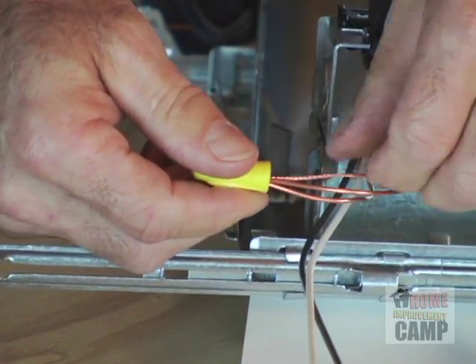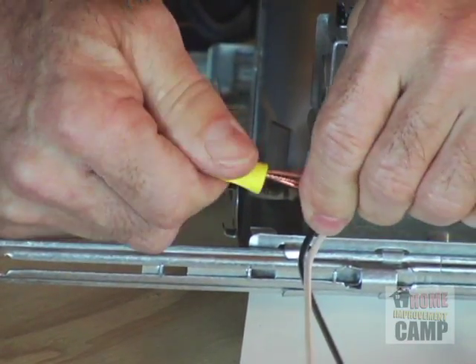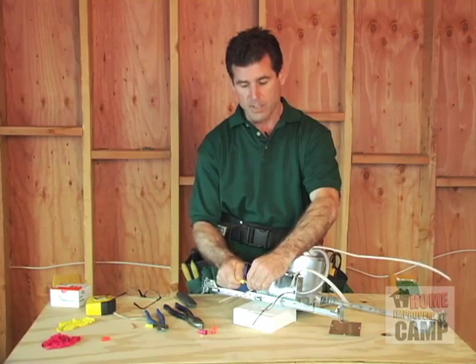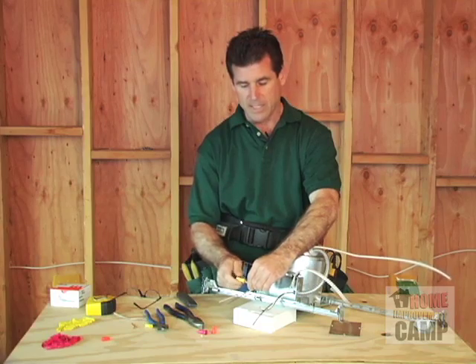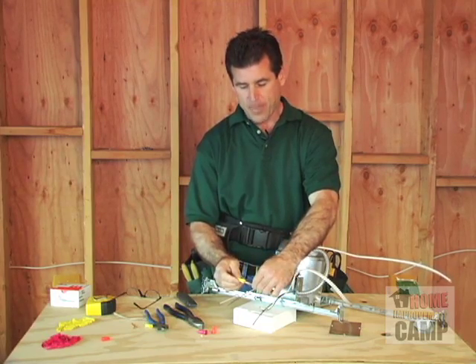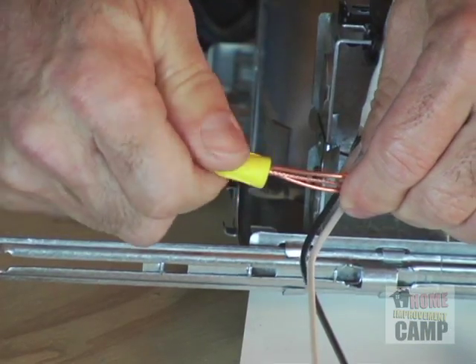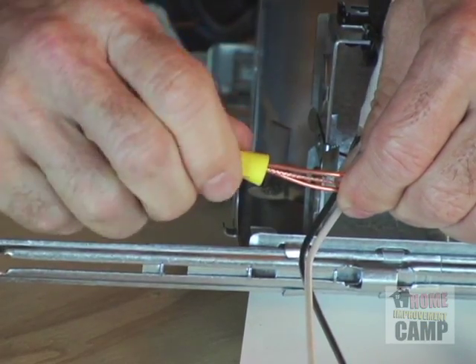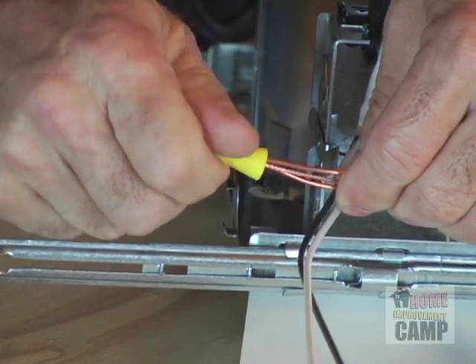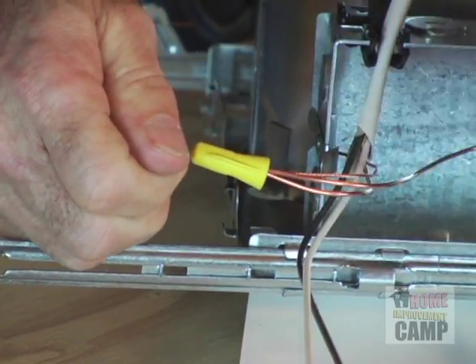So I give a little tug on the wires, make sure they're well connected, make sure the wire nut's on all the way, good and tight. This particular brand of wire nut actually has a torque setting, believe it or not. When you turn this wire nut past a certain point, it just starts slipping because they don't want you to over torque the wire.